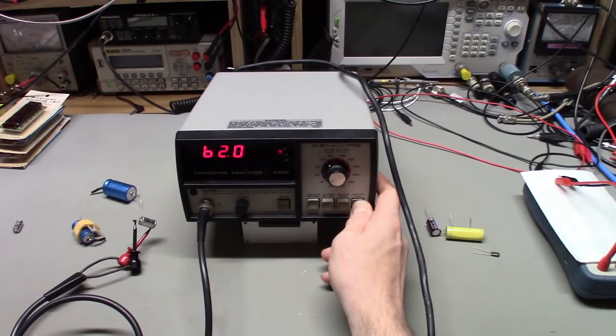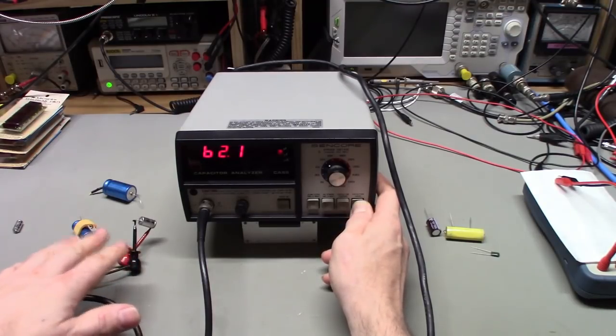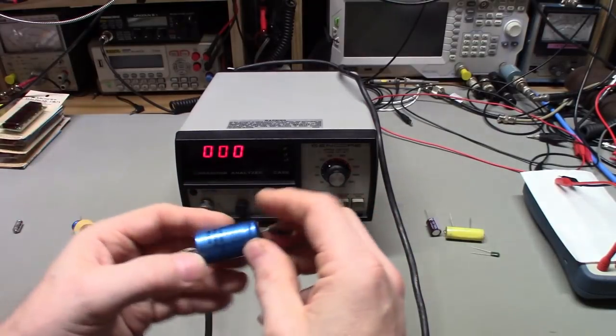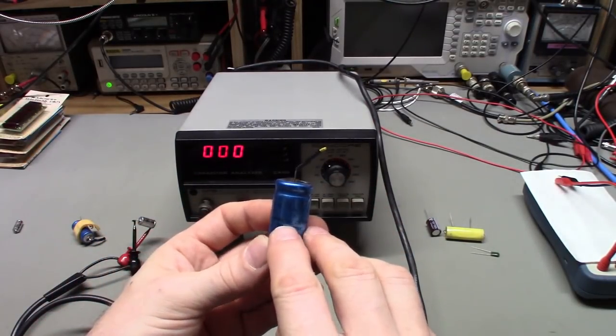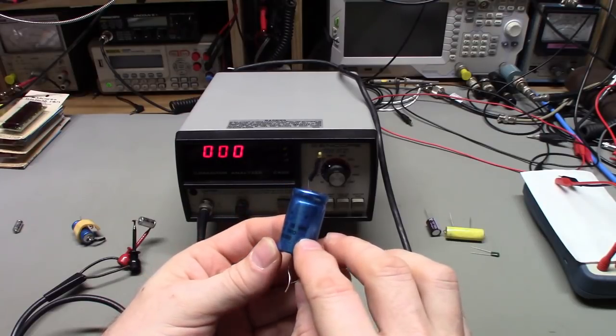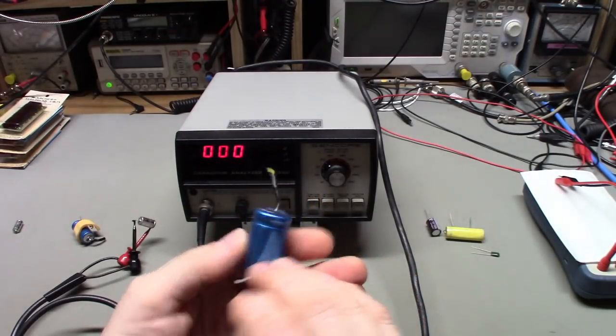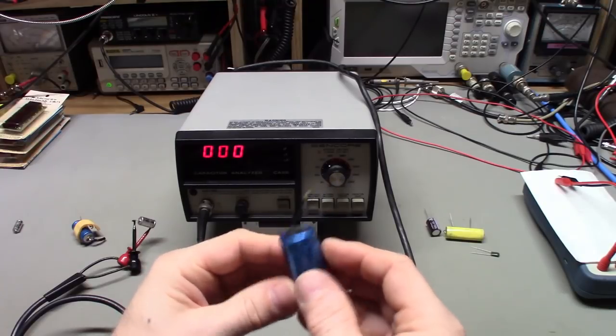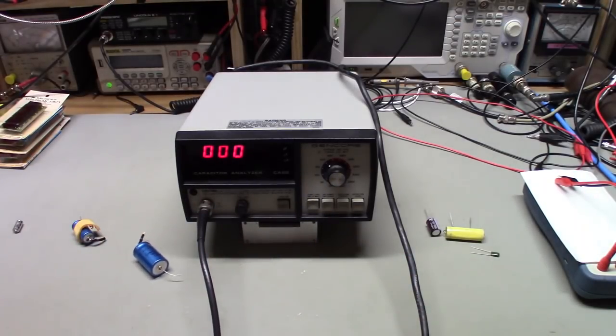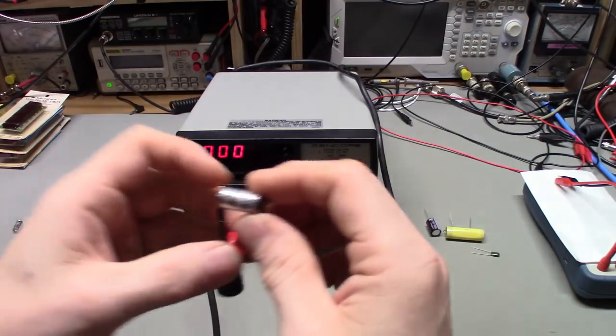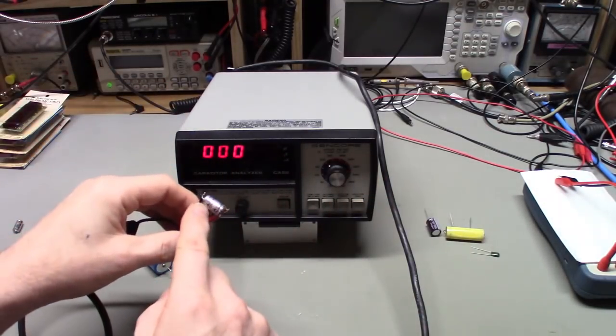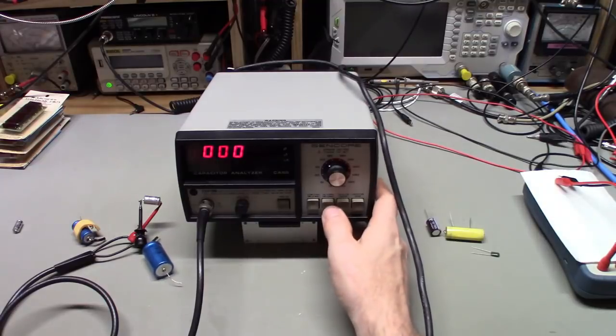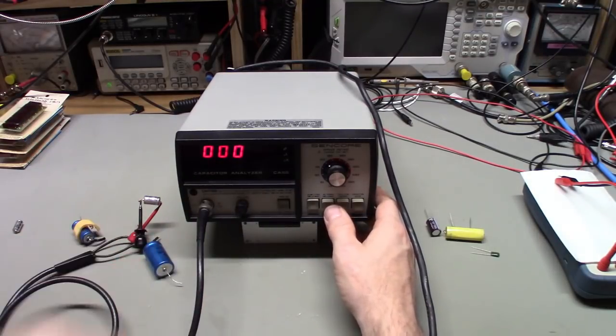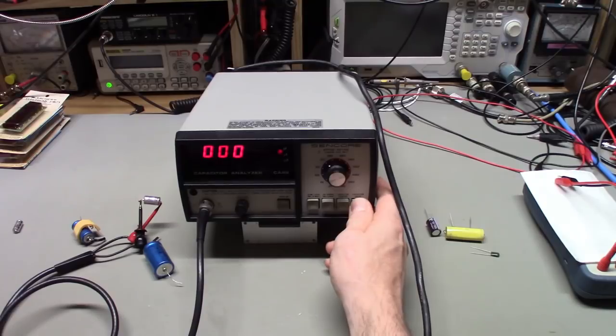We can see that one's higher than what it's rated for, which is usual with most electrolytic capacitors. If you look at them, you can see this one's 2000 microfarads, 25 volts, and it doesn't have a percentage on it. Well, that's kind of strange. Most of them do. Does this one? This one doesn't either. That's actually, I guess, more commonplace nowadays. They'll have the percentage or the tolerance for the capacitor. So don't be surprised if you see it higher or lower than what it's rated, especially electrolytics. That's fairly common. But that one's testing at like 62.1, 62 microfarads.